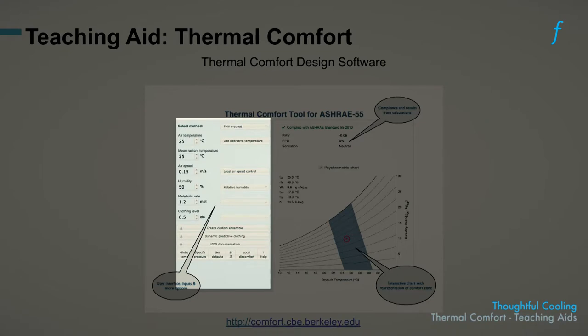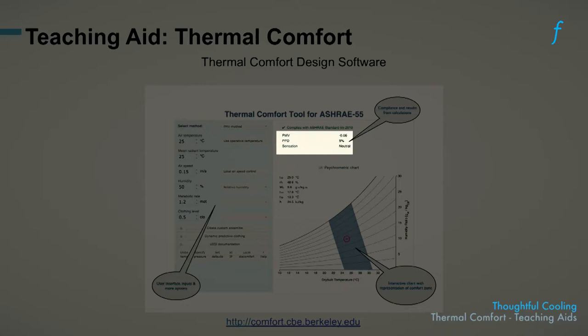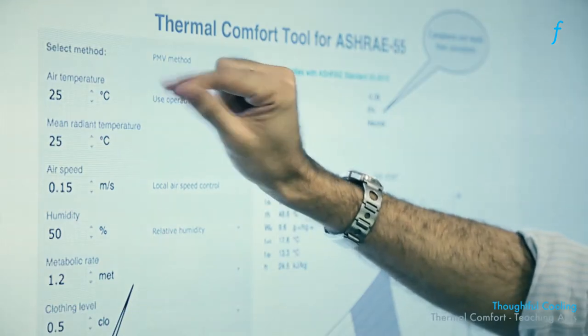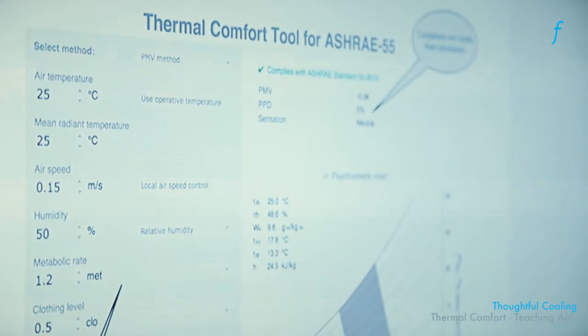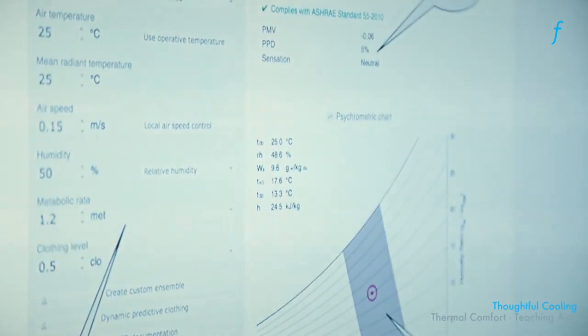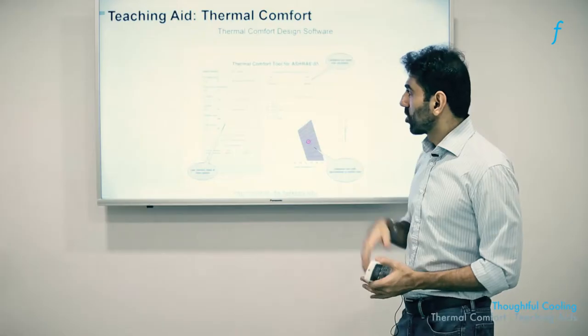As you can see, here are the input variables we already spoke about. This tool immediately provides you with the Predicted Mean Vote value and the Percentage of People Dissatisfied. This allows you to do iterative calculations — you can change things like air temperature, air speed, and humidity levels to see whether we can meet PMV and PPD targets at the most efficient level.